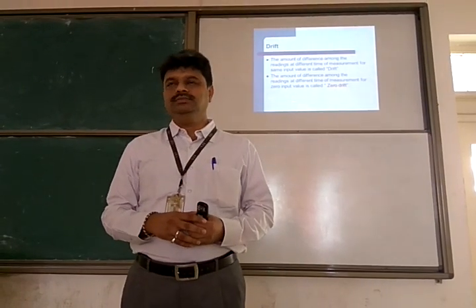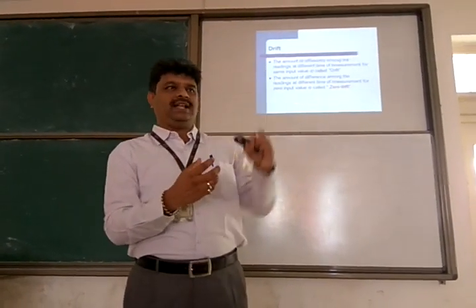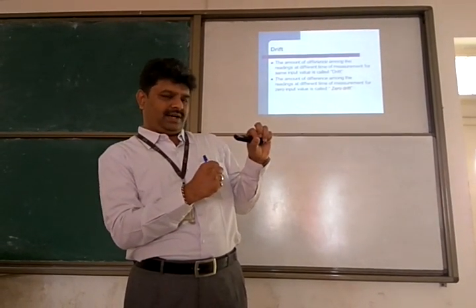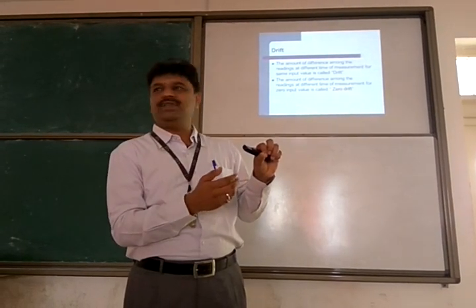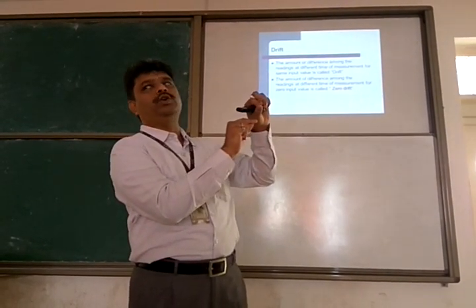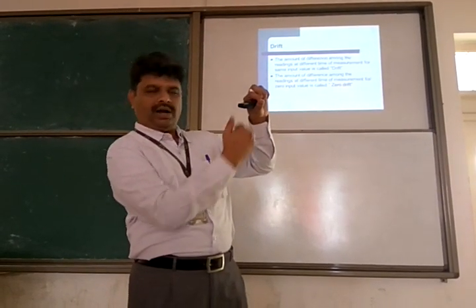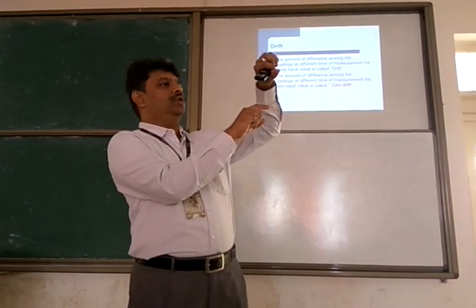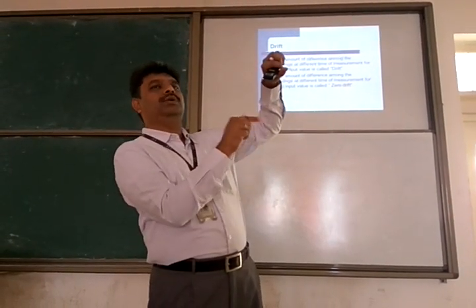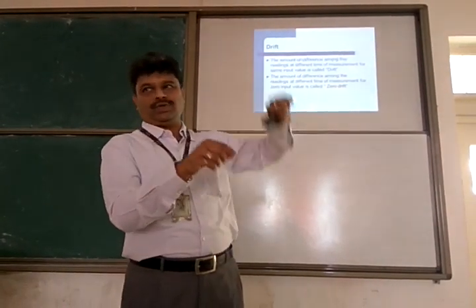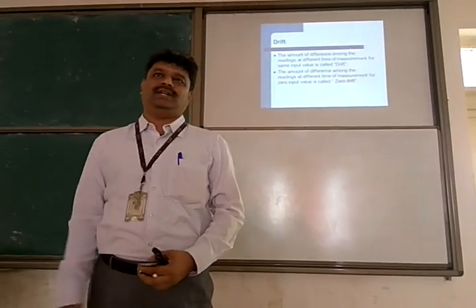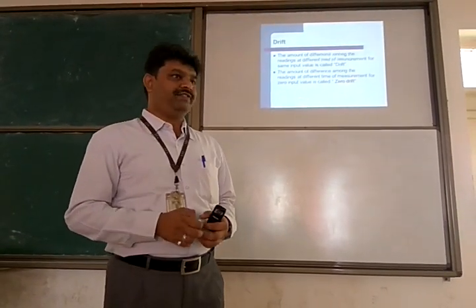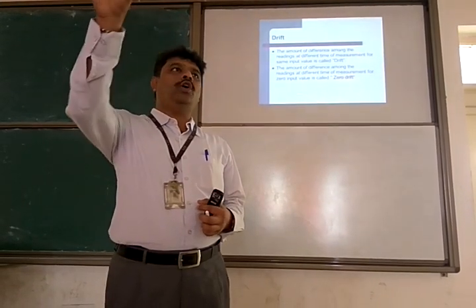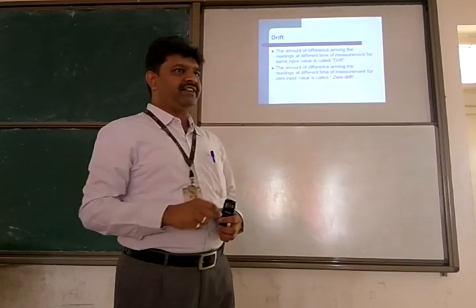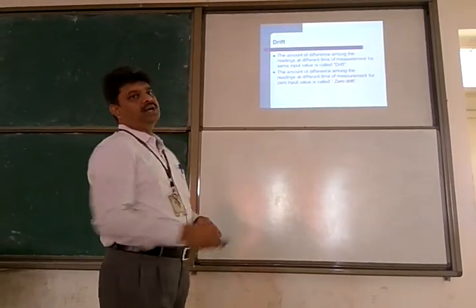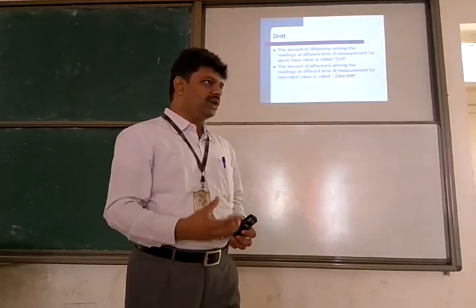For example, take a spring balance. The stiffness of the spring would have slightly expanded permanently, maybe because of misuse. So instead of 0, initially it will show 0.2 kilograms. Without any weight, it will show 0.2 kilograms. You put 1 kilo, it will show 1.2 kilograms. You put 2 kilograms, 2.2 kilograms. So 0.2 will always be the error in the instrument. That's called drift. If it is computed when no input is given, that is called zero drift. So for any instrument, before starting, you should look for zero drift.